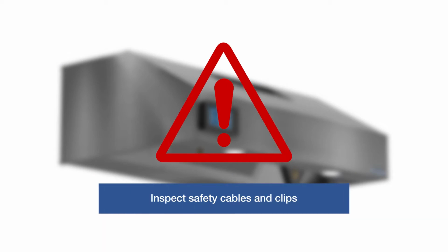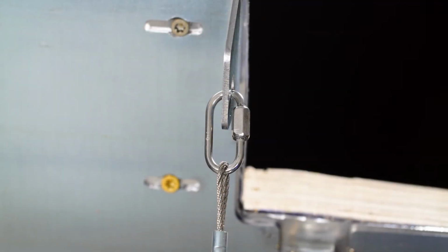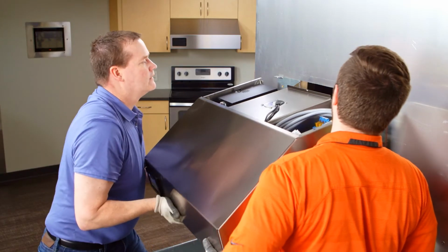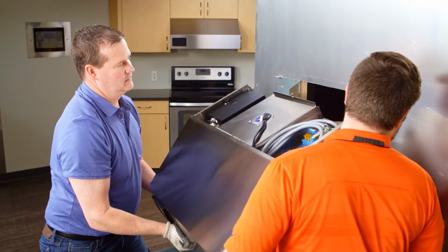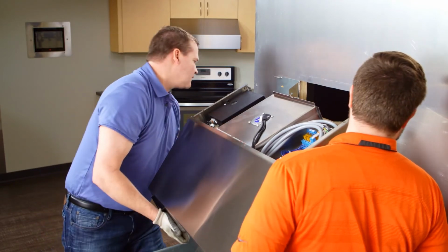Release the clamps one at a time, pushing up on the bottom of the front lip of the hood to ease release. This hood weighs up to 93 pounds, so be sure to inspect the safety cable and its clips to ensure it's been correctly installed and secured. With both clamps released, keep upward pressure on the front edge of the hood and pull this safety bolt downwards with a firm grip on the black handle. After the bolt is released, slowly let the hood pivot down until the cable is tight and supporting the hood weight.